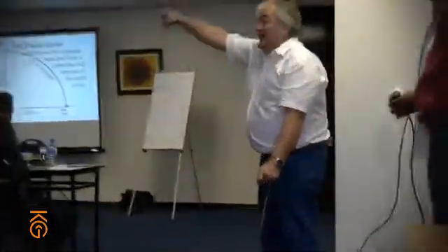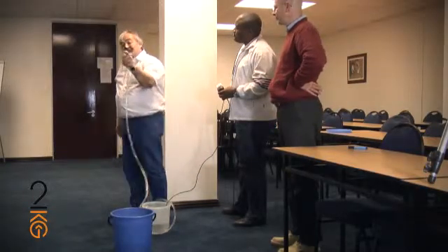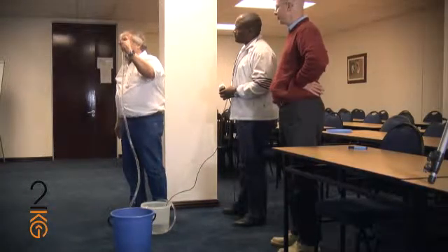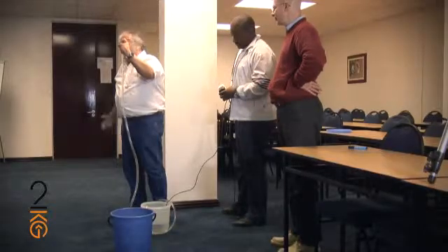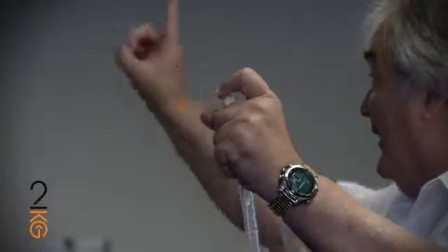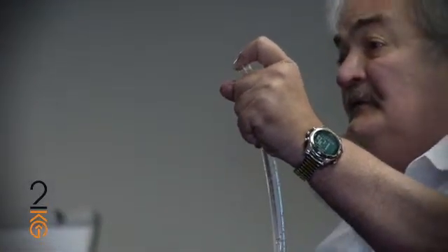Now this pump just went from the right end of the curve all the way to the left end of the curve. You see, I've got maximum pressure against my finger and zero flow. I am all the way back there at shutoff head, totally independent of the elevation.